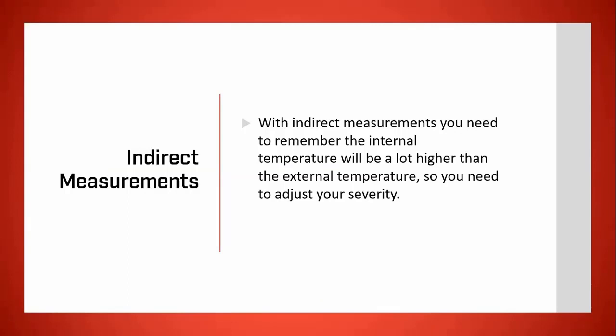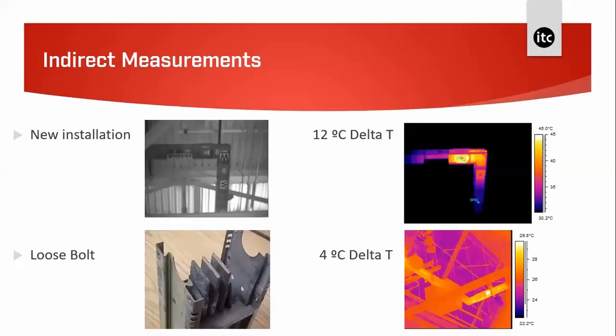With indirect measurements, remember that the internal temperature will be much higher than the external temperature — so we need to adjust our severity criteria if we cannot overcome the indirect nature of our survey. Looking at these two busbar installations, the camera is doing a good job picking up elevated temperature. We can measure a delta T, but the heating source may be some distance away, making it difficult to estimate the internal temperature accurately.